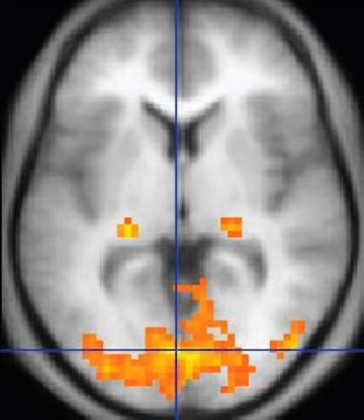The contrast between different tissues is determined by the rate at which excited atoms return to the equilibrium state. Exogenous contrast agents may be given to the person to make the image clearer. The major components of an MRI scanner are the main magnet, which polarizes the sample, the shim coils for correcting shifts in the homogeneity of the main magnetic field, the gradient system which is used to localize the MR signal, and the RF system, which excites the sample and detects the resulting NMR signal. The whole system is controlled by one or more computers.